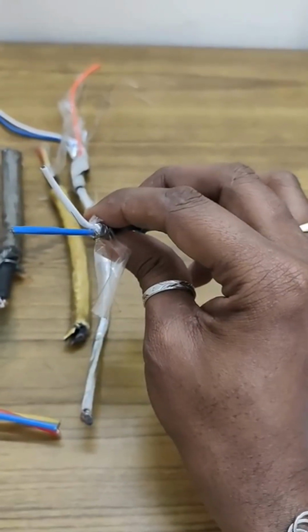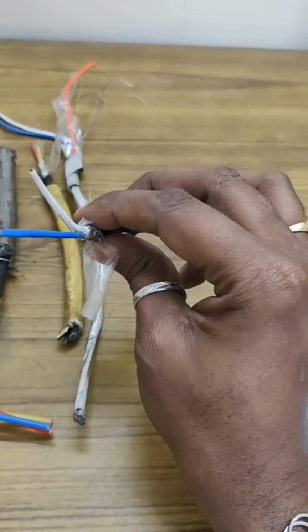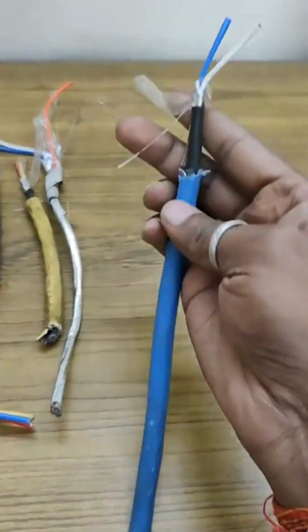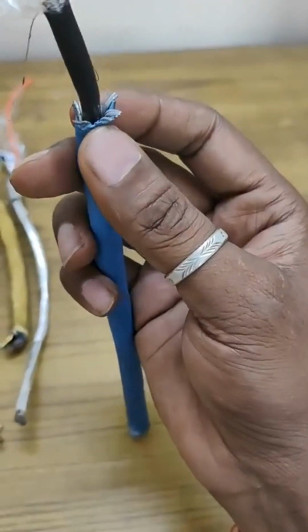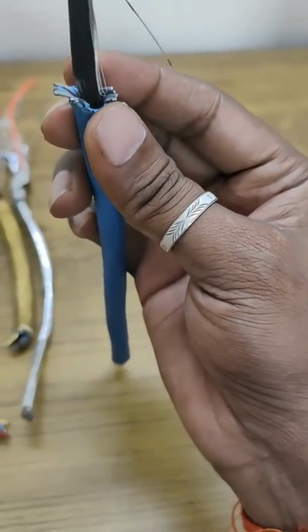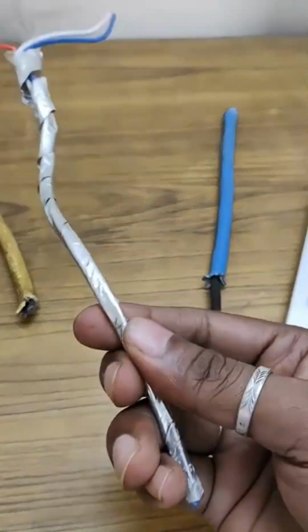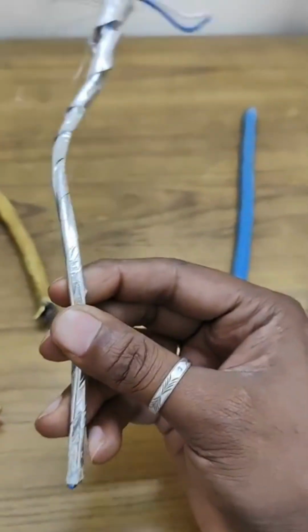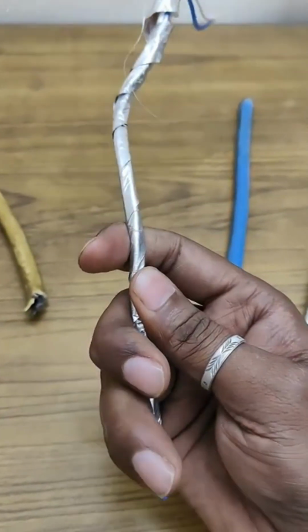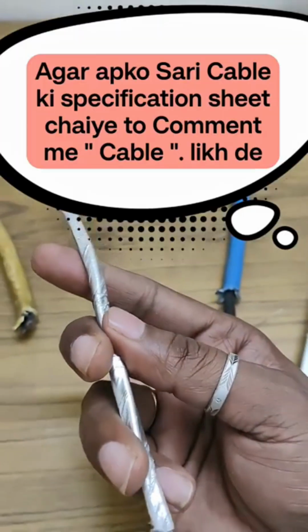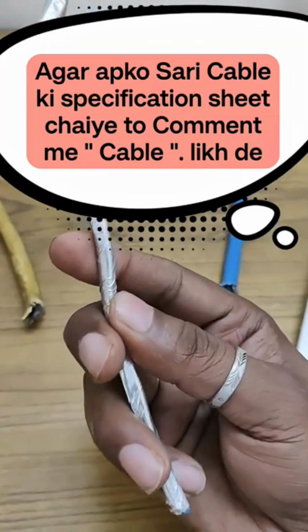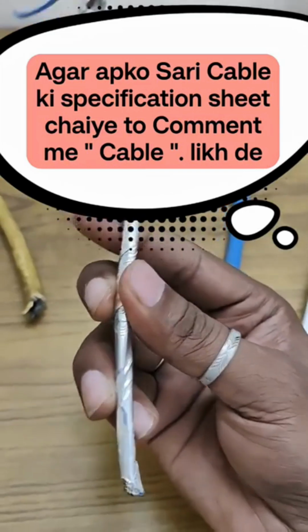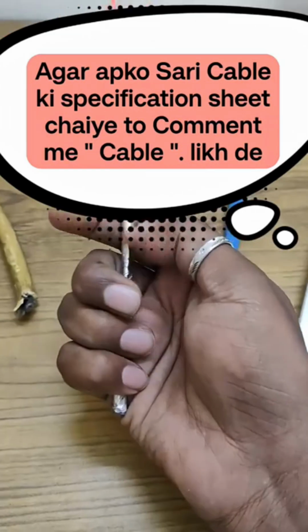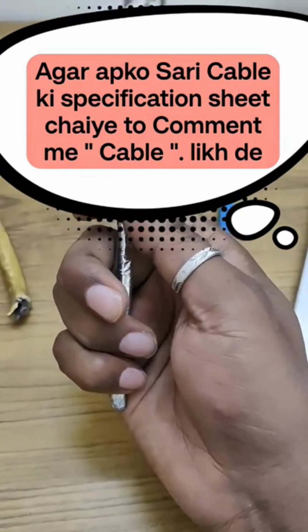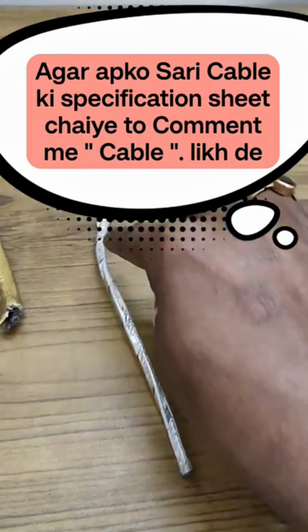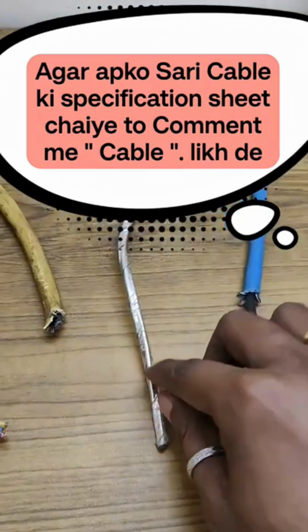Now, let's talk about the second important point, shielding. The shield coverage of the cable is very important. Typically, good instrumentation cables have shield coverage between 85% and 95%. If the shield coverage is low, the cable can pick up electromagnetic interference. This may cause unstable readings in transmitters or other instruments, especially in areas where VFDs are installed. In such environments, it becomes extremely important that the cable shield coverage is close to 95%, just like the cable shown here. Another thing you will notice inside this cable is a drain wire.